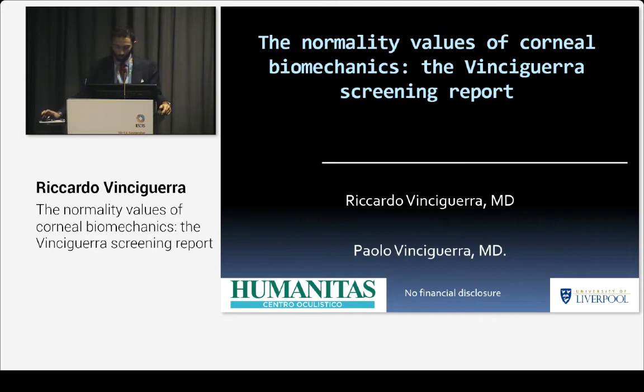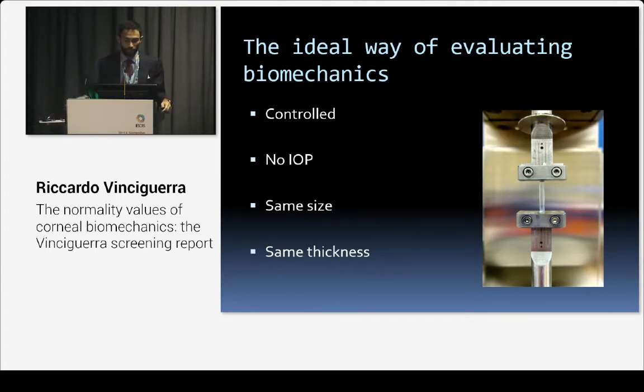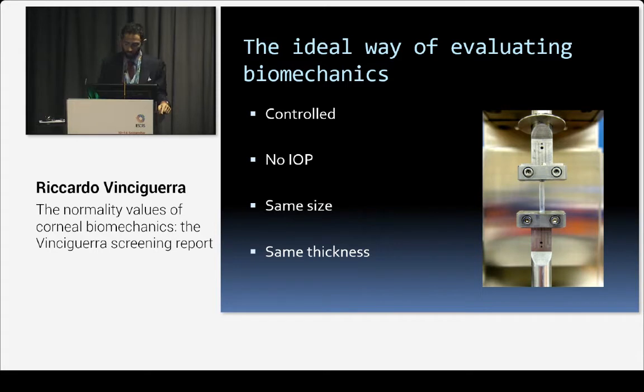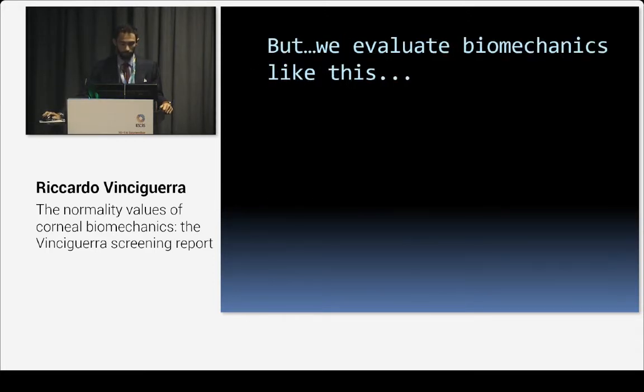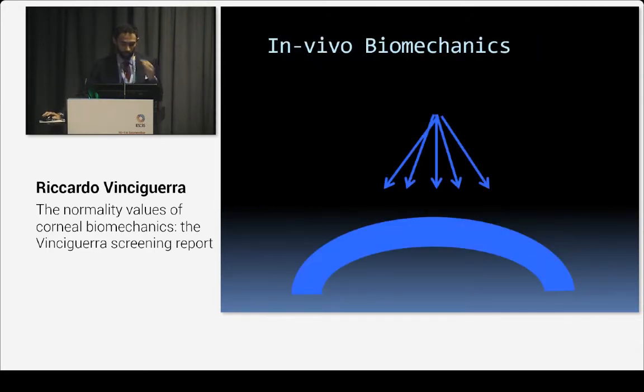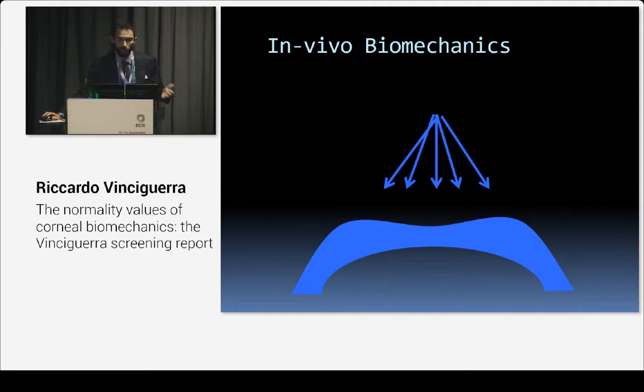Thank you, Cinzia, for the introduction and for making my life much easier after this explanation. The ideal way of evaluating biomechanics would be in a controlled stress-strain setting with no IOP and the same size and thickness. Unfortunately, this is not possible with alive patients. So what we have to do is use an air puff to deflect the cornea, and from this we have to evaluate biomechanics.